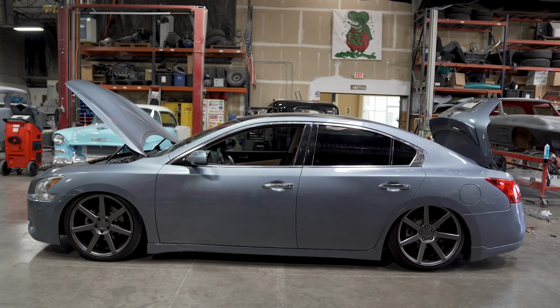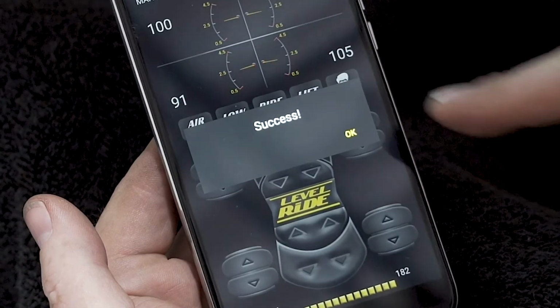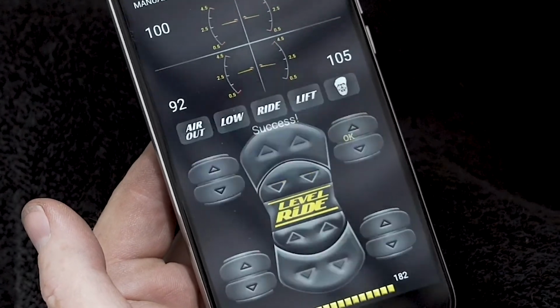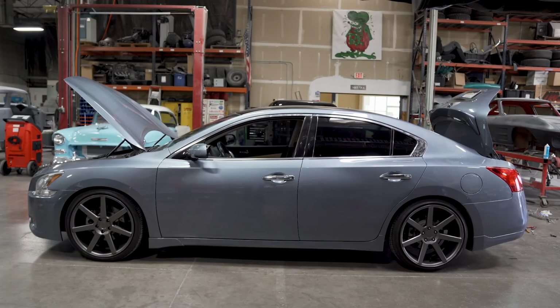Calibration will continue after the first drop once the tank pressure is increased above 185 psi. When calibration is complete, success OK will come up on the screen. Press OK, and at that point you can begin setting up your own presets.